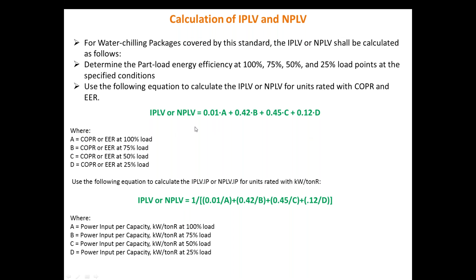But if you don't have COP or EER, and instead you have to use kilowatt per ton of refrigeration, then you simply inverse the formula. That is, IPLV or NPLV equals 1 divided by (0.01/A + 0.42/B + 0.45/C + 0.12/D). Only an inverse and slight modification in the formula is required when using kilowatt per ton instead of COP or EER. This is the simple formula to evaluate the performance of your refrigerator based on this.